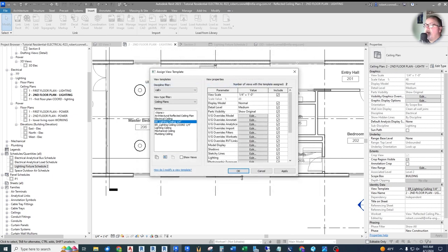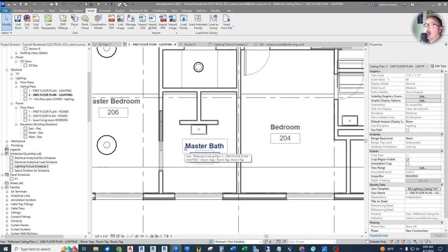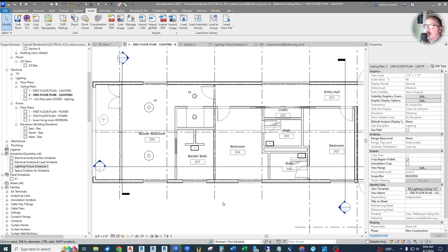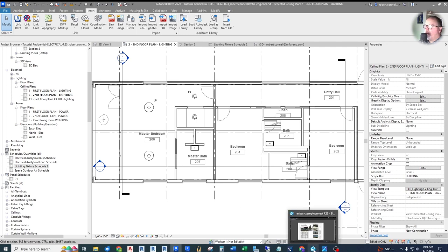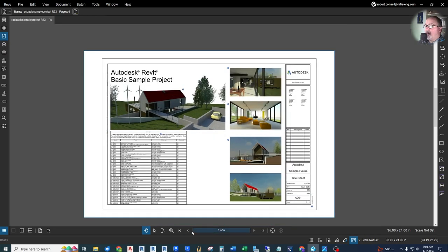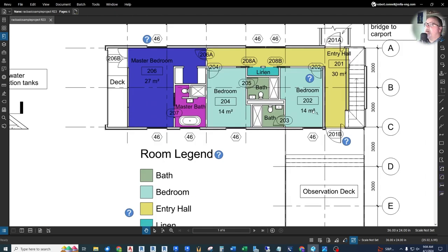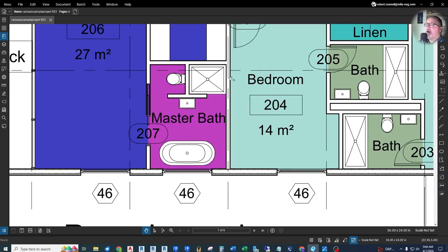In the bathrooms, we want some wall-mounted fixtures above the plumbing. Our view range is cut at two feet, so it should show plumbing. We had previously turned off plumbing to keep the view clean, but we can turn it on briefly in Visibility/Graphics under the Revit Link, enabling Plumbing Fixtures. We can also refer to an architectural PDF for reference — the shower is here, toilet here. The designers want a vanity light over the sink, pendants in the other areas, with a pendant rated for a wet environment over the tub and in the shower.